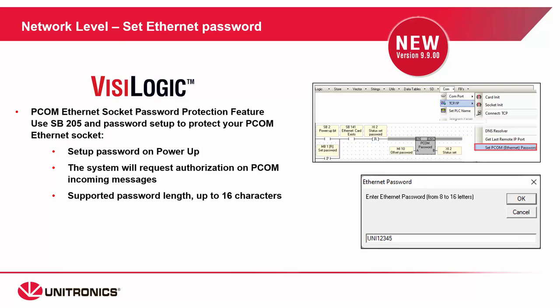The next feature released is a PCOM Ethernet socket password. This password is a requirement in the new version and it should be set on power-up SB 205. The password supports a length up to 16 characters. When a new device tries to connect to the PLC over an Ethernet socket, it will be prompted to enter the password.